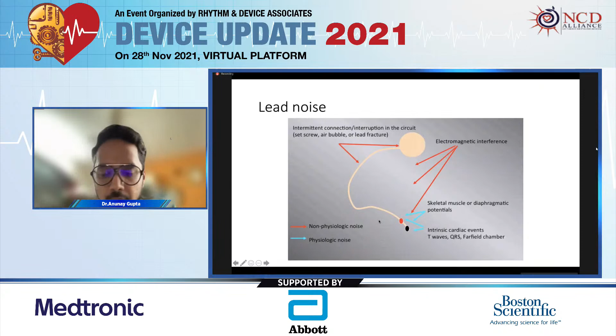So this schematic diagram helps us understand where all the problems can happen. In the lead, it can be either due to a lead fracture or a loose set screw, or the presence of an air bubble in the header. EMI can interfere with both the high frequency far field and near field. And even intrinsic cardiac events can be mis-sensed as noise and lead to oversensing.